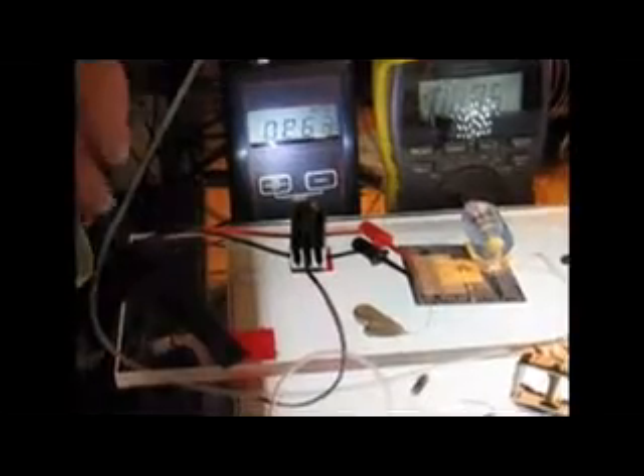and the manometer is on overload from it being about 2 or 3 kilopascals. I'll disconnect it. Now the bubble's deflated. I don't have a seal. I stick the tubing back together, and now I'll okay, now I have a seal, and it's sealed at about 200 pascals.